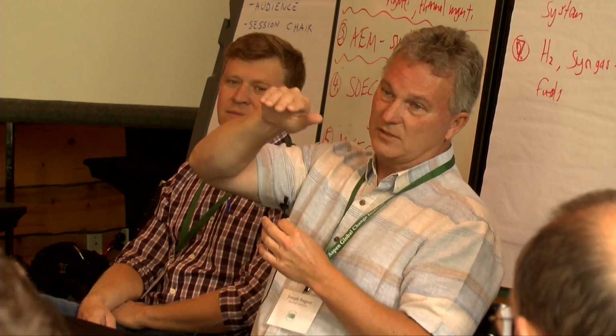So with that, we hope to find out, within tolerance of forecasting, because the system uses weather downloads and forecasts of prices and loads every 15 minutes, so there's going to be imperfection there. You never get to theoretical perfection in hindsight. But once we train the system and see how close we can sustain actual operations to the theoretical optimum, then with persistence monitoring we watch that. And if it starts to deviate, say we were able to get within 3% of optimum, but we start to get to 4 or 5, we say, hey, what's going on?